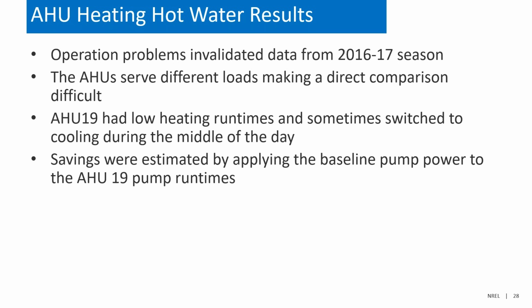Another big issue that we had was when we originally selected the building, the pumps had very long run times in the heating season, but we found that they were not meeting the discharge air temperature set point and were essentially not meeting the load requirements. And so we had to put the project on pause, retro commission the whole facility, and then come back and do the demo.